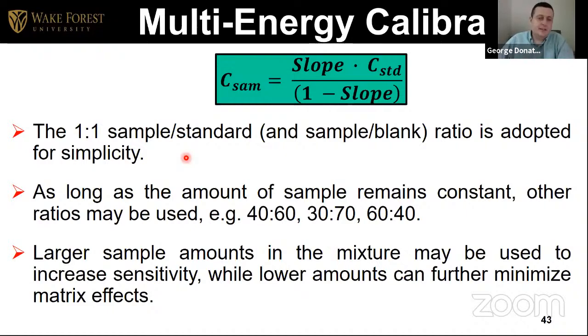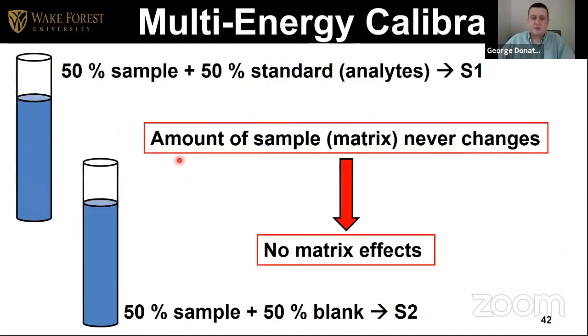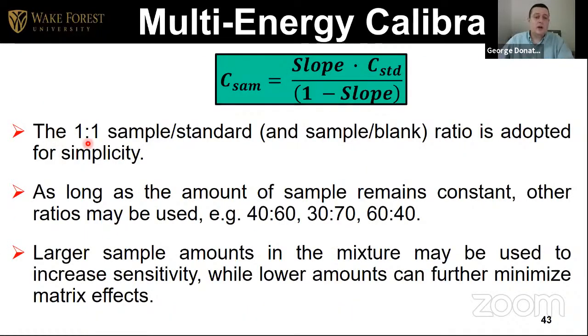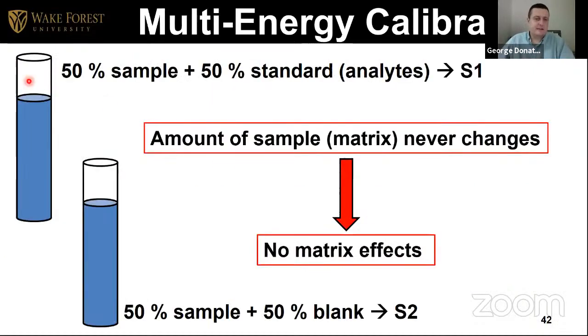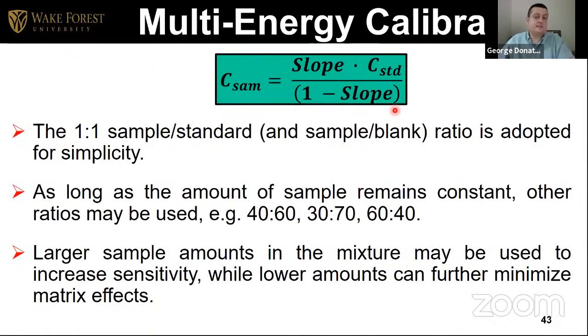Another thing about this, you don't need to mix those two solutions. The autosampler goes to the first solution, measures it at several wavelengths, goes to the second solution, measures several wavelengths, and then you do the calibration. The one-to-one sample-standard mix, because we use half-half, is just for simplicity. It doesn't need to be like that. It can be 40-60, 30-70, 60-40. It depends on what you want to do.